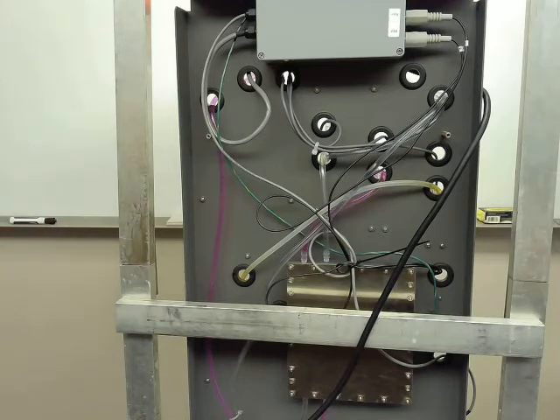I think the only other real maintenance thing, we talked about extended shutdown. Tubing replacement is the other thing, which we have in the manual as about a year. Again, that can change wildly based on the sample that's coming into the analyzer. If you have real clean, ultra pure water coming through it, you might not have to do it every year. There's other places where we probably have to do it every couple months because the sample's just that dirty. Flow will start to be affected, how the sample runs through the analyzer and flows past our electrodes. But the tubing kit that we supply has all the tubing pre-cut, so it's just taking them off one by one and putting the replacement tubing back in its place.